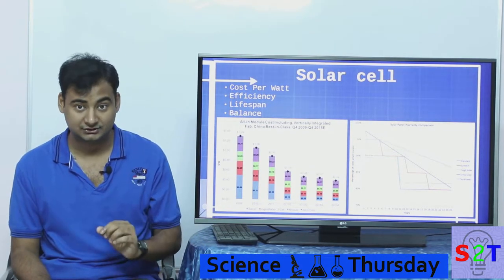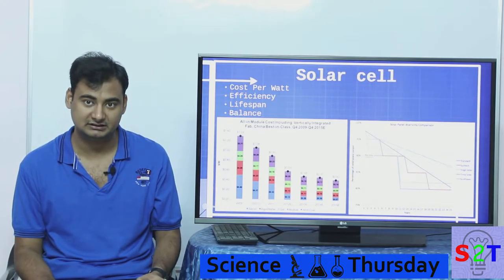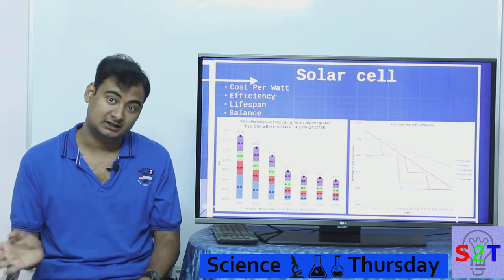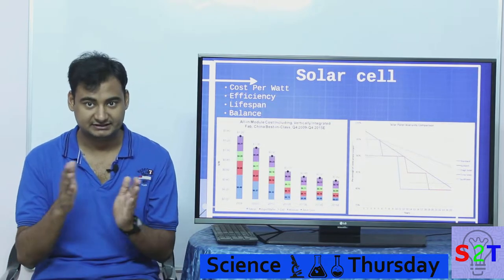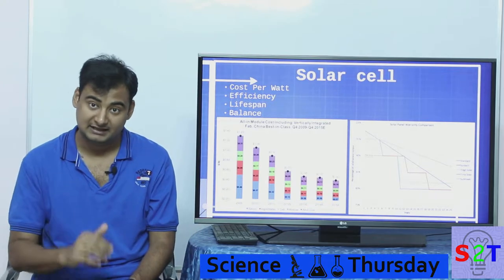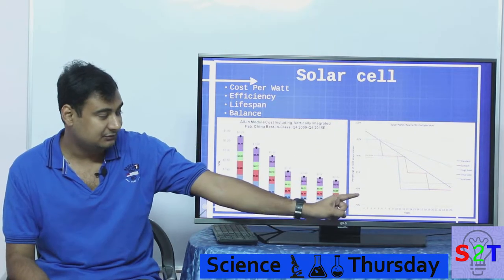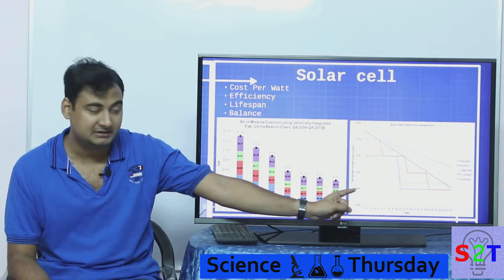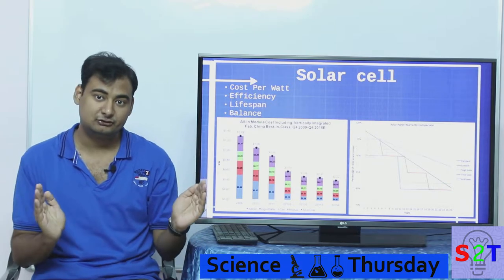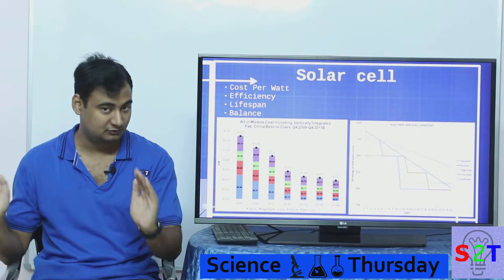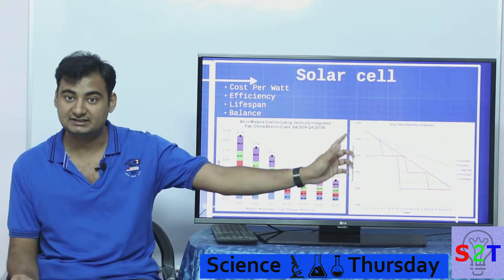The third factor is lifespan — often neglected for small-scale but very crucial for large-scale industrial applications. Earlier, solar cells would lose upwards of 1 to 5% capacity per year, so they wouldn't last very long. Nowadays, reputable manufacturers give warranties on capacity for 25 years, guaranteeing you will have upwards of 80% of the original output. So a 100-watt panel should still be an 80-watt panel 25 years from purchase.